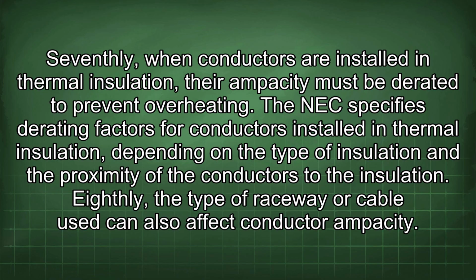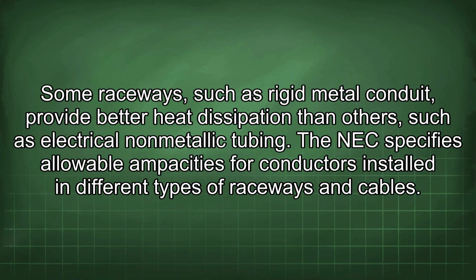Seventhly, when conductors are installed in thermal insulation, their ampacity must be derated to prevent overheating. The NEC specifies derating factors for conductors installed in thermal insulation depending on the type of insulation and the proximity of the conductors to the insulation. Eighthly, the type of raceway or cable used can also affect conductor ampacity. Some raceways, such as rigid metal conduit, provide better heat dissipation than others, such as electrical non-metallic tubing. The NEC specifies allowable ampacities for conductors installed in different types of raceways and cables.